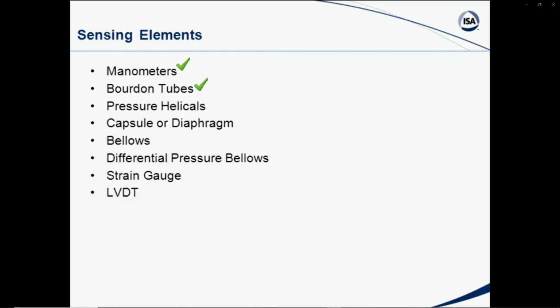A lot of the pressure gauges, field gauges that you see in the field, are either Bourdon tubes or helicals or capsules or diaphragms, depending upon, is it a high pressure like thousands and thousands of psi, or is it a medium pressure, 100 to 150 pounds, or is it inches of water, something like that. These are used many times in the local pressure gauges that you see throughout industry and throughout different types of process units. Or it could be really low. We might use a bellows, or there is a differential pressure bellows.